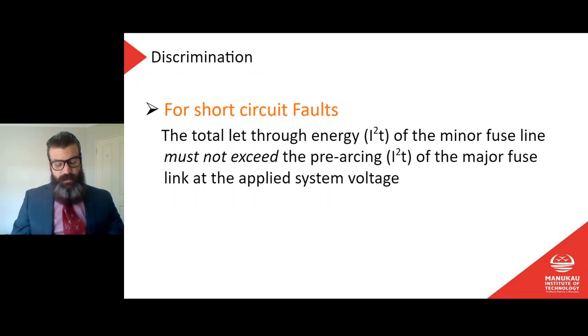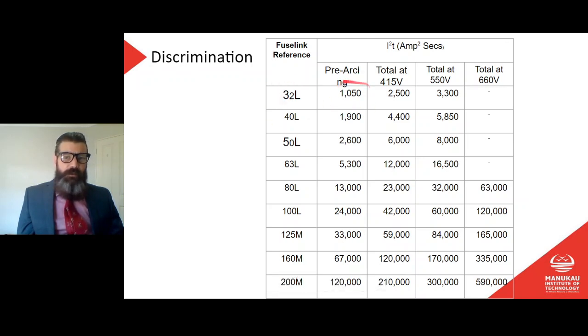So that means that the first fuse, the energy that it lets through before it completely breaks, must be less than the pre-arcing of the next fuse back, and any subsequent fuses back from that point. It's not the easiest concept to understand, but hey, it is what it is. So what do we got here? Fuse link 32, pre-arcing is, so this is our I squared T, current times time. Let's not get too fussy about what that means. What we need to worry about is the absolute numbers.